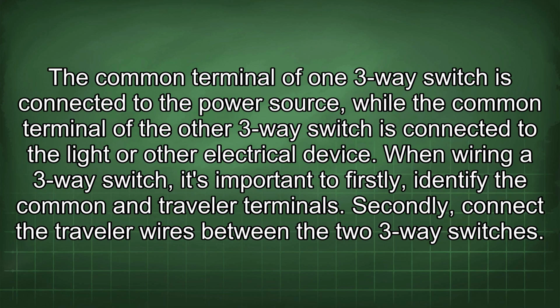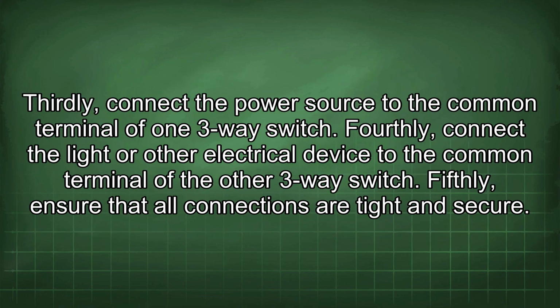The common terminal of one three-way switch is connected to the power source, while the common terminal of the other three-way switch is connected to the light or other electrical device. When wiring a three-way switch, it's important to firstly identify the common and traveler terminals. Secondly, connect the traveler wires between the two three-way switches. Thirdly, connect the power source to the common terminal of one three-way switch. Fourthly, connect the light or other electrical device to the common terminal of the other three-way switch.